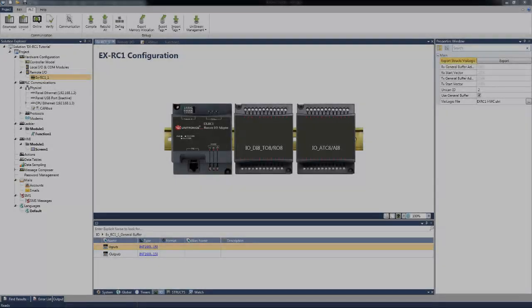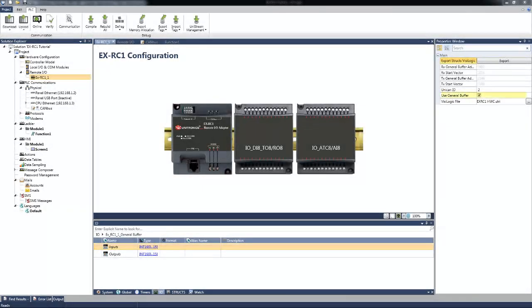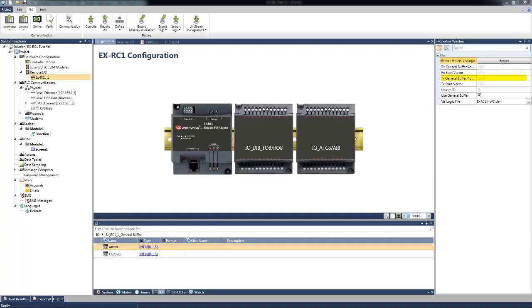If we select to use the General Buffer, the Output array of the General Buffer struct will be set automatically to the address MI1144 in length of 16 registers. And in order to send data from the EXRC1 to the Unistream, we need to include in UnicanSend function the data to destination address MI1000.